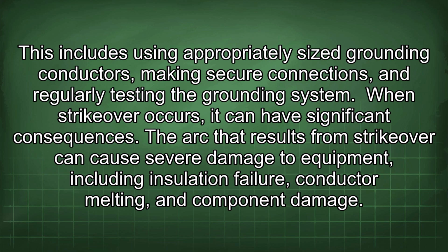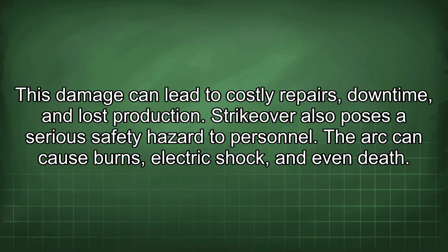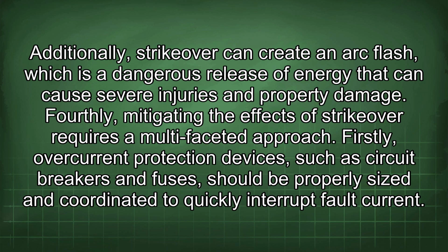When strikeover occurs, it can have significant consequences. The arc that results from strikeover can cause severe damage to equipment, including insulation failure, conductor melting, and component damage. This damage can lead to costly repairs, downtime, and lost production. Strikeover also poses a serious safety hazard to personnel. The arc can cause burns, electric shock, and even death. Additionally, strikeover can create an arc flash, which is a dangerous release of energy that can cause severe injuries and property damage.